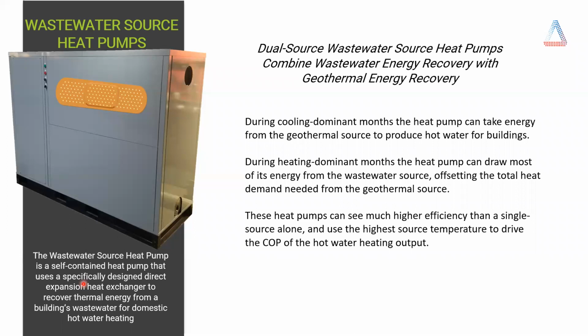During the heating dominant months, the heat pump can take its primary energy source from a wastewater source. So using this, we can offset the heat demand that would otherwise be seen from the geothermal source as well. By not pulling all of that domestic hot water heating energy from the geofield, it allows more energy to be used for the building heating source, as opposed to taking all of that energy for the building. Having that energy sharing can really have a positive impact on the overall design of the system.